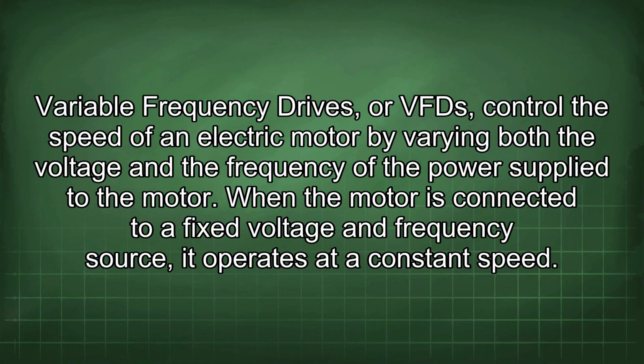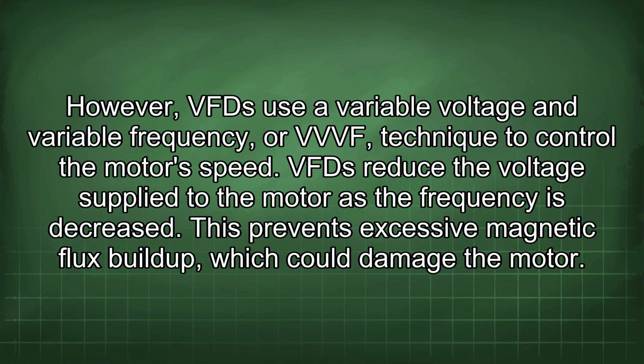Variable frequency drives, or VFDs, control the speed of an electric motor by varying both the voltage and the frequency of the power supplied to the motor. When the motor is connected to a fixed voltage and frequency source, it operates at a constant speed. However, VFDs use a variable voltage and variable frequency, or VVVF, technique to control the motor's speed.